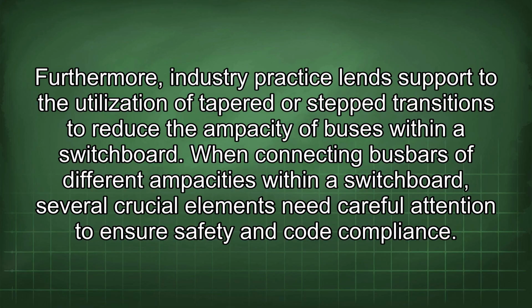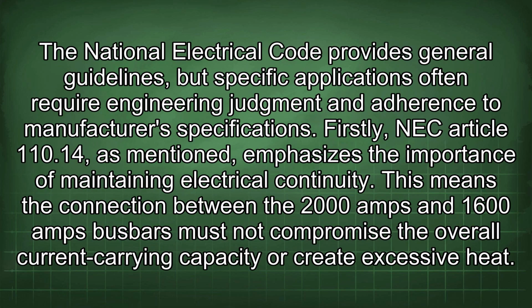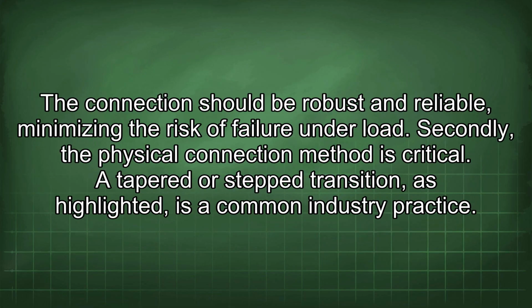When connecting bus bars of different ampacities within a switchboard, several crucial elements need careful attention to ensure safety and code compliance. The National Electrical Code provides general guidelines, but specific applications often require engineering judgment and adherence to manufacturer specifications. Firstly, NEC Article 110.14, as mentioned, emphasizes the importance of maintaining electrical continuity. This means the connection between the 2000 amps and 1600 amps bus bars must not compromise the overall current carrying capacity or create excessive heat. The connection should be robust and reliable, minimizing the risk of failure under load.